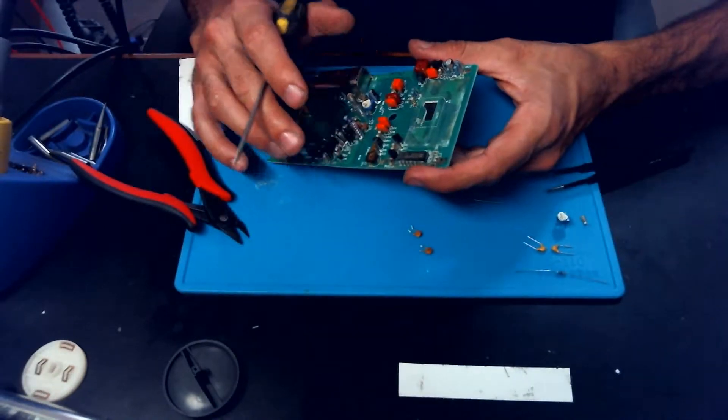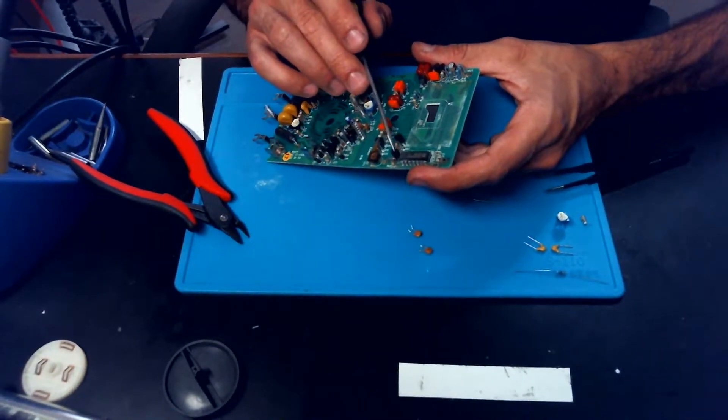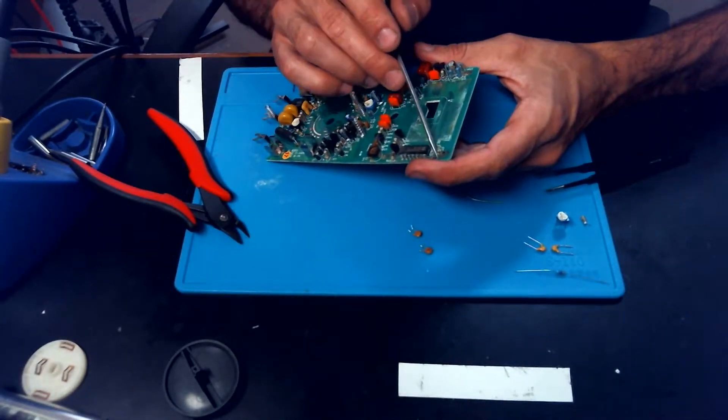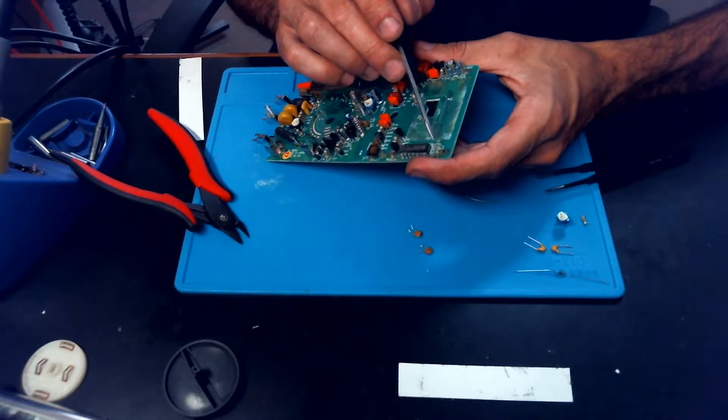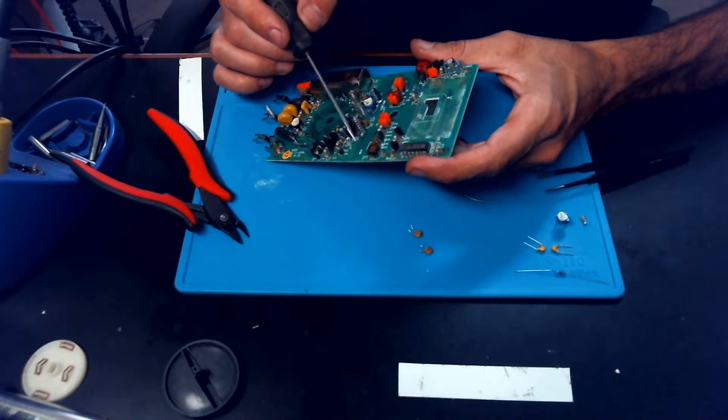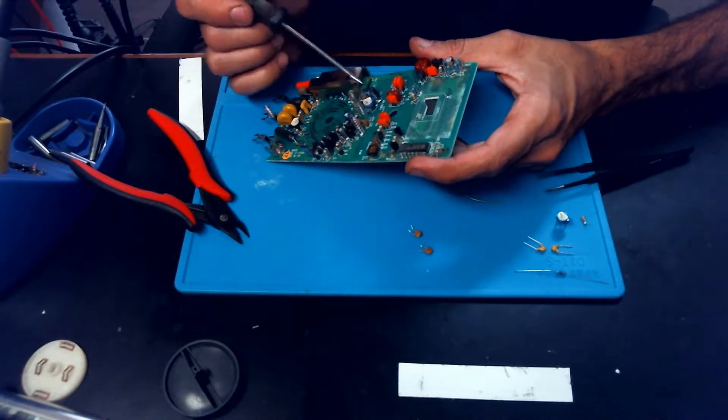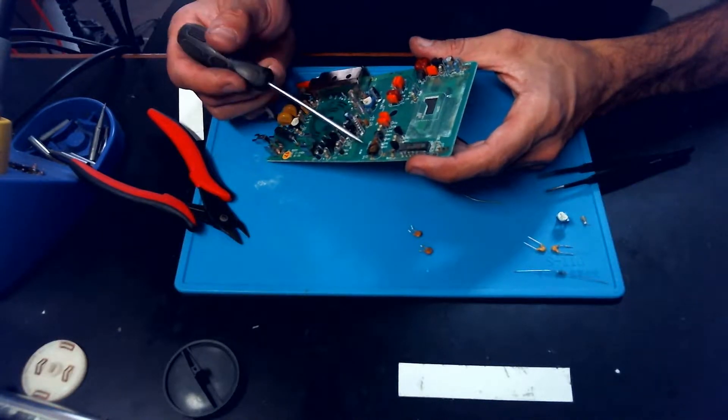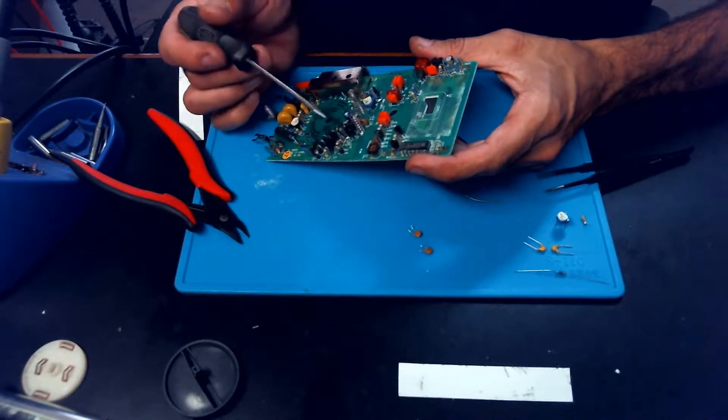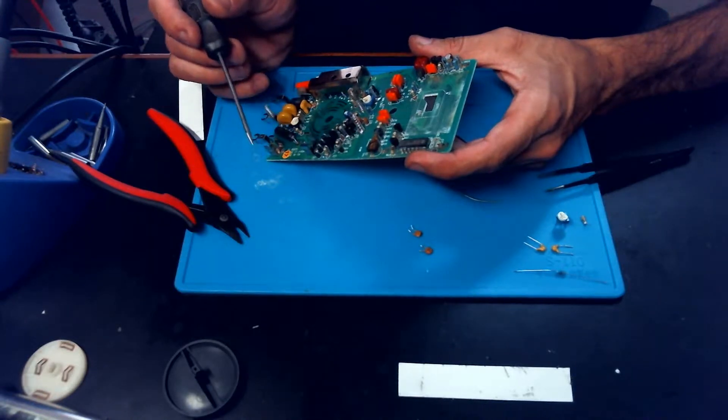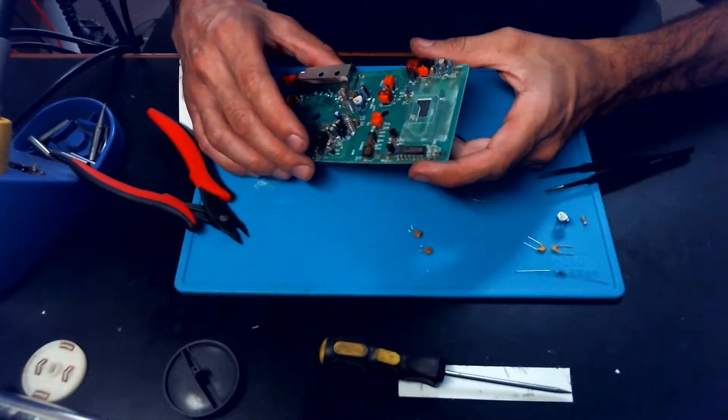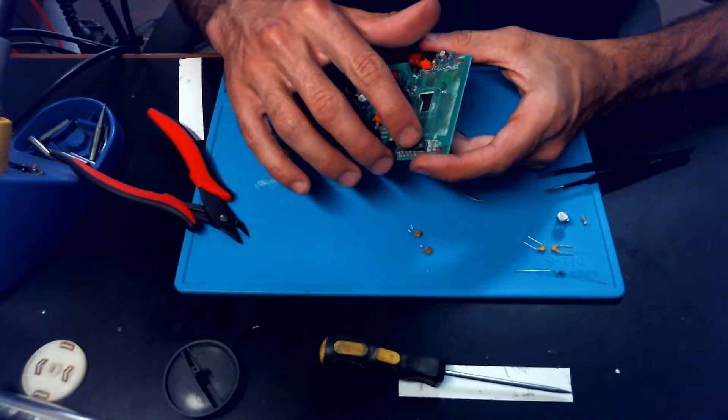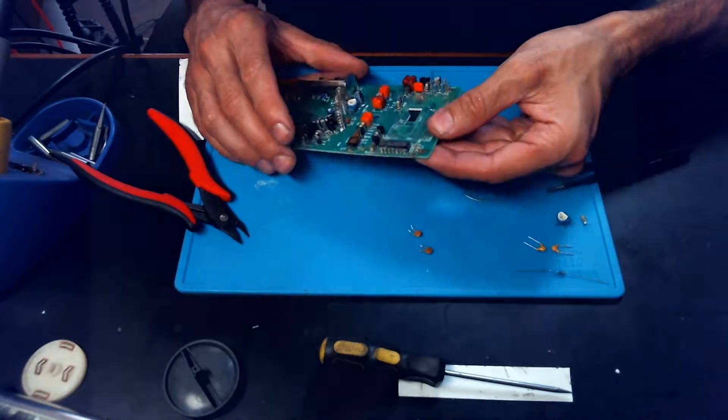But that may actually be the reason why the meter wasn't turning on was because it had no continuity here and it couldn't find the ground. But we'll go ahead and replace the rest of the components anyways because I know that some of these are obviously bad. But I just wanted to show that to y'all right whenever I found it.